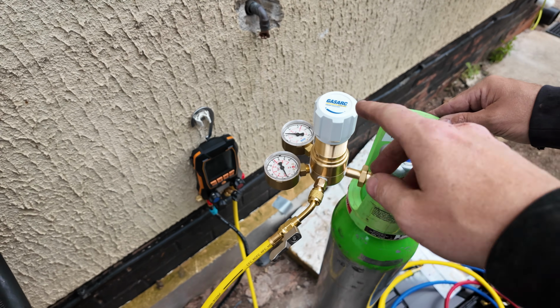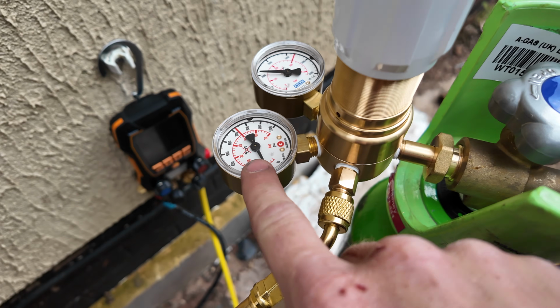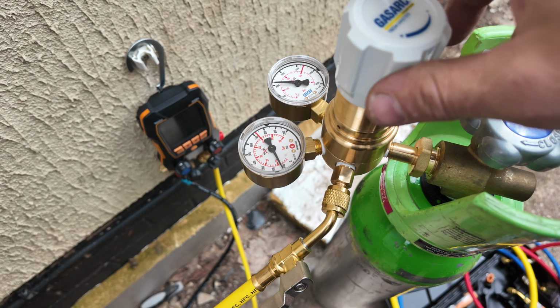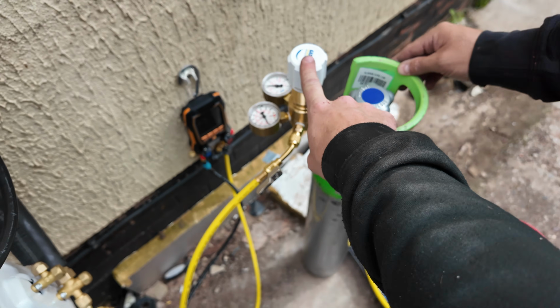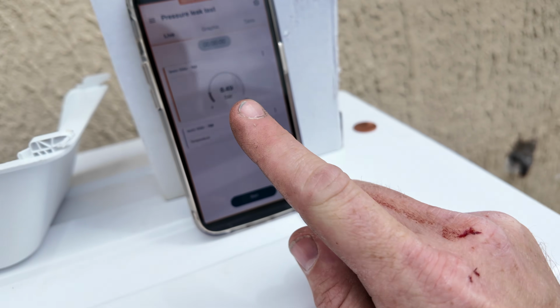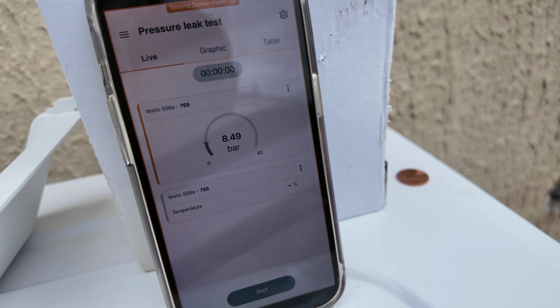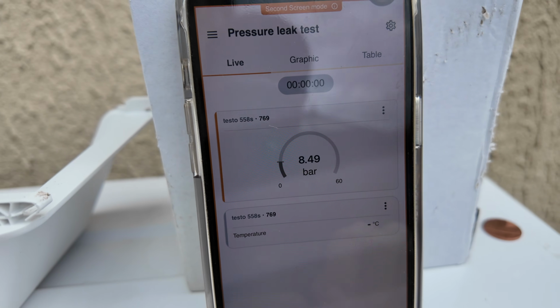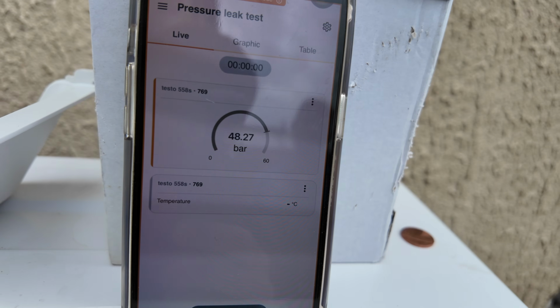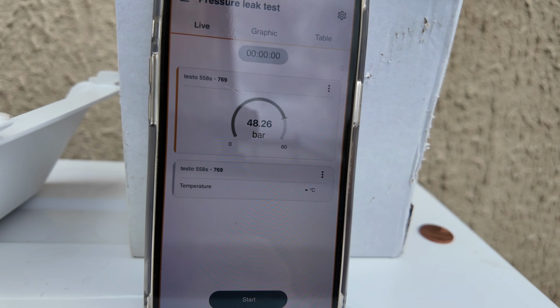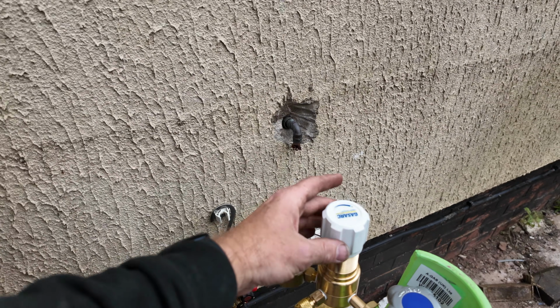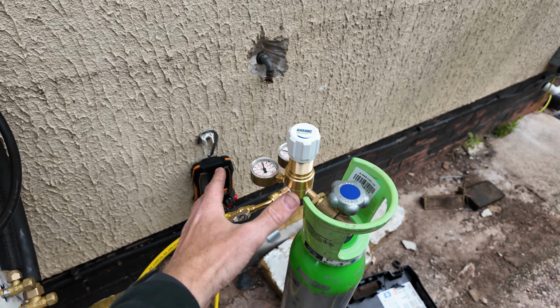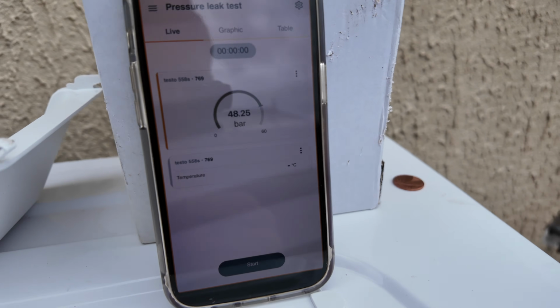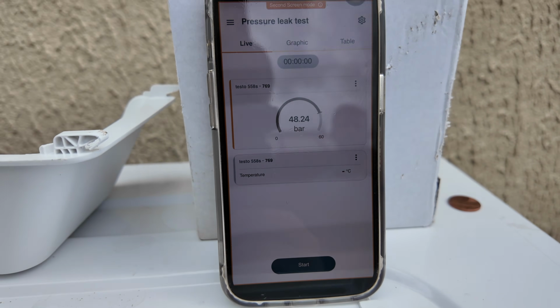With this part here, you can put it up to whatever pressure you want, so you can start increasing that. Chris, do you want to increase that? I can show people on here what we're getting because this is the Testo app - you can use it on your gauge here or on here. So we watch that, and we want to get it up to 48 bar. There you go, you can see we've got it to 48 bar. That's loosened off now, so no more nitrogen is going through. That's literally 48 bar in the system, and that's your strength test.